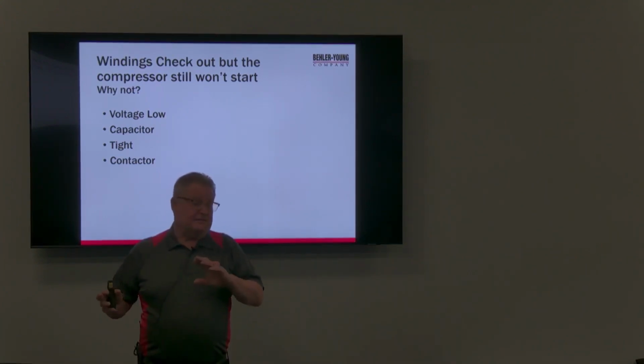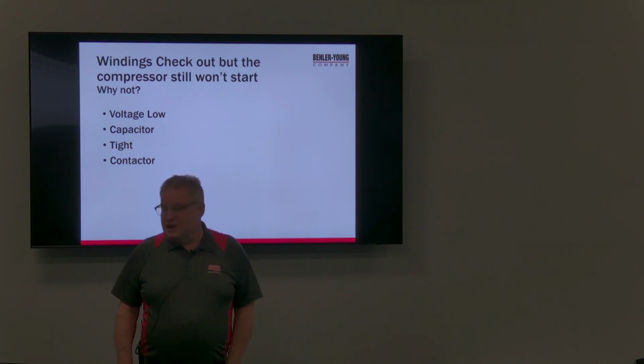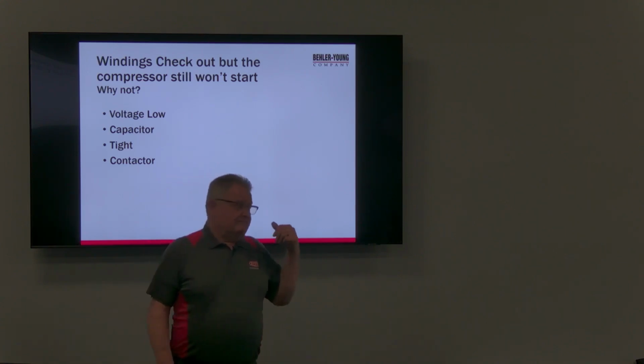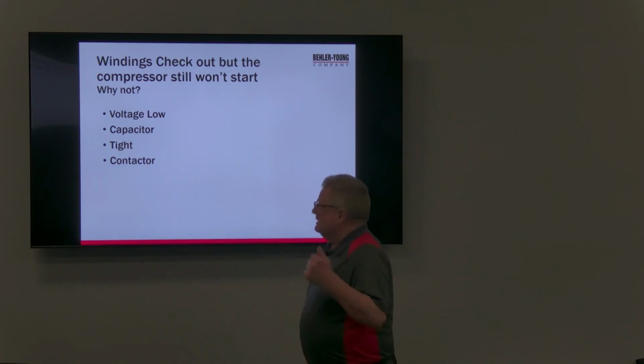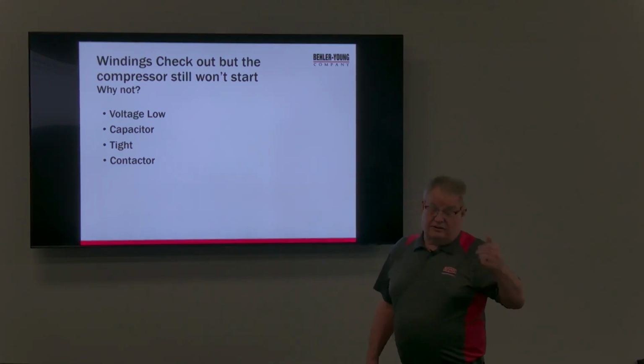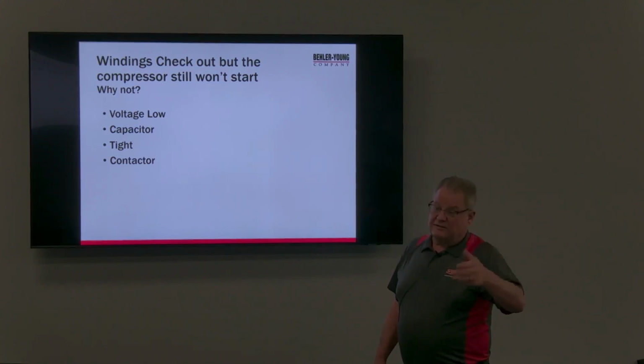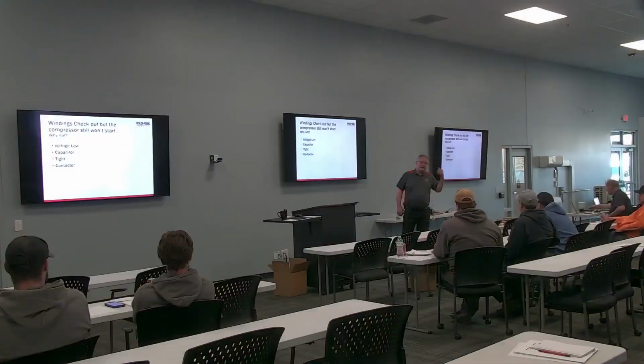And sometimes you'll have a 25% current imbalance. And it's really strange how it works. You would think it was the motor doing it, but it's actually happening before the motor. So that's just a big thing. So if you're losing motors, you're losing especially control boards or VFDs, we want to look at putting protection on there as far as phase monitors on 3-phase. We have single phase voltage monitors. So it's definitely worth looking at that.